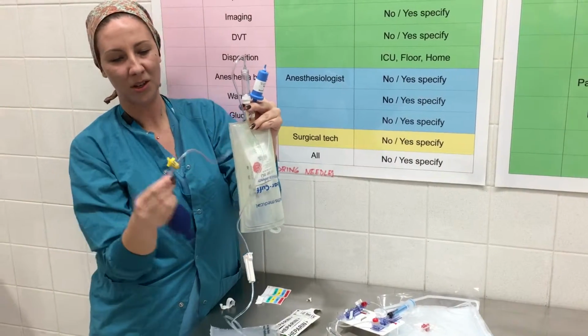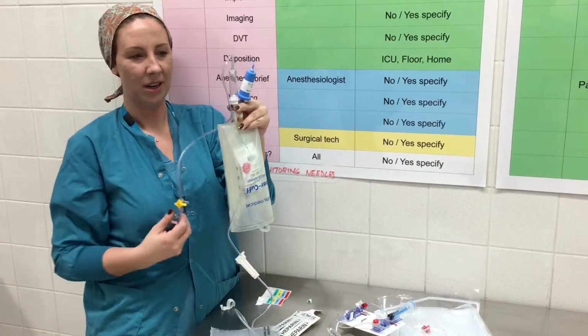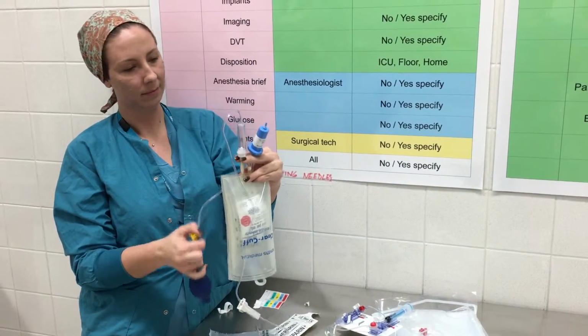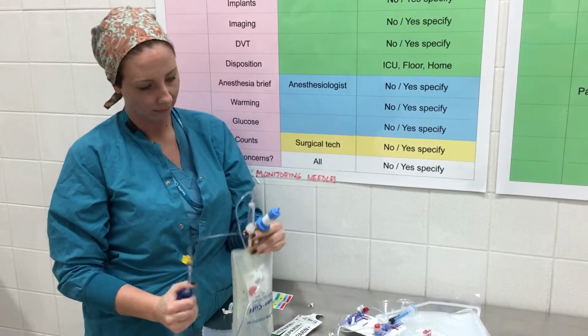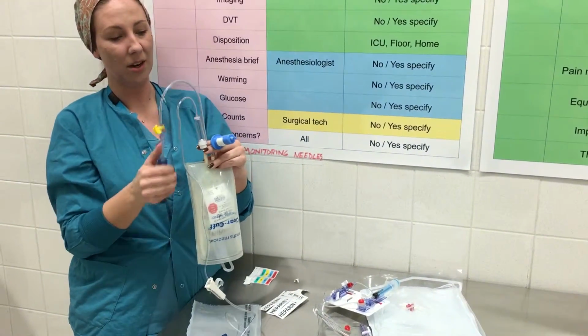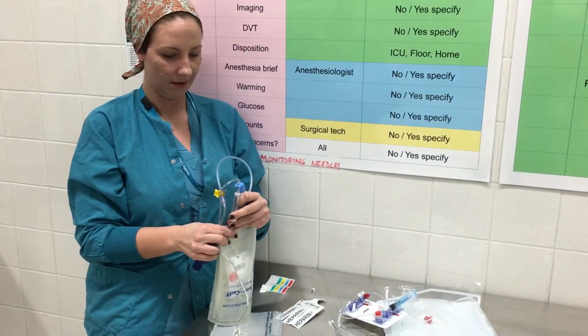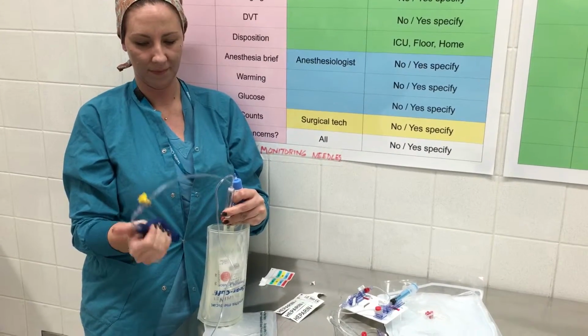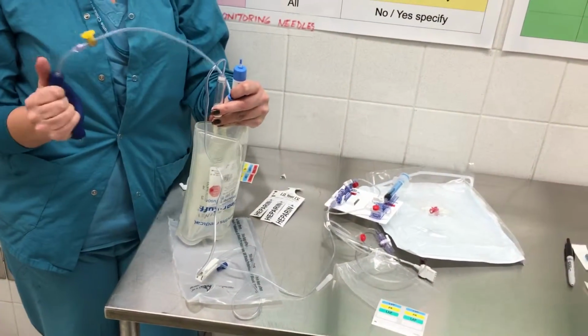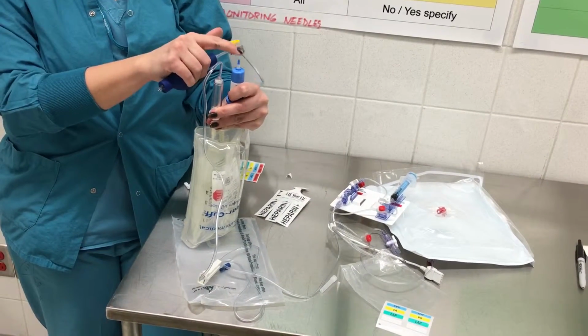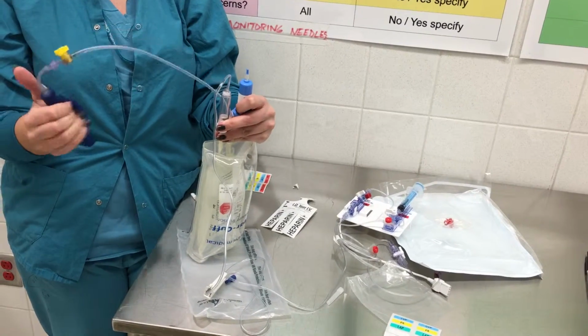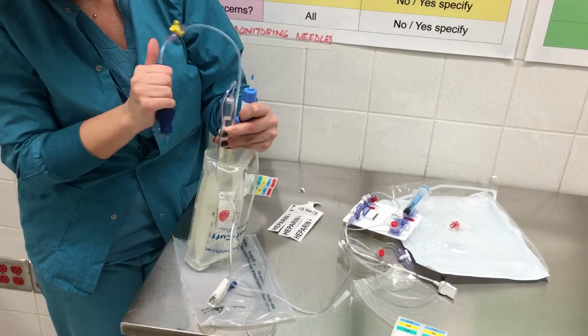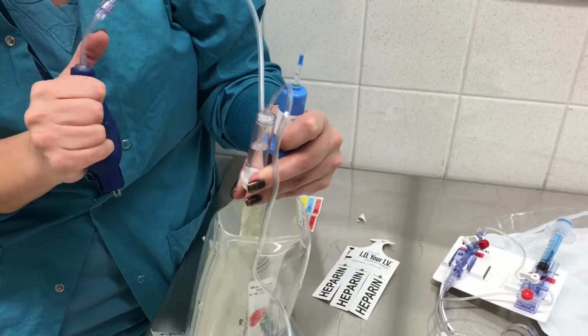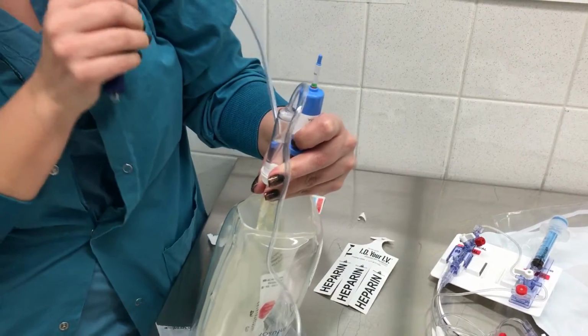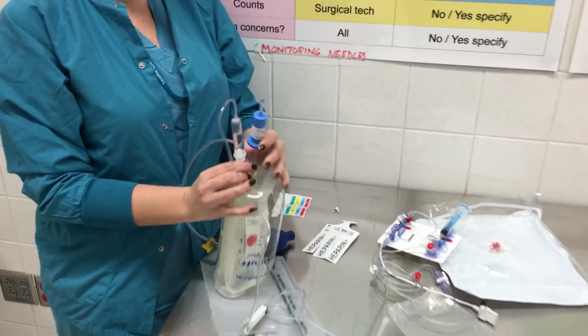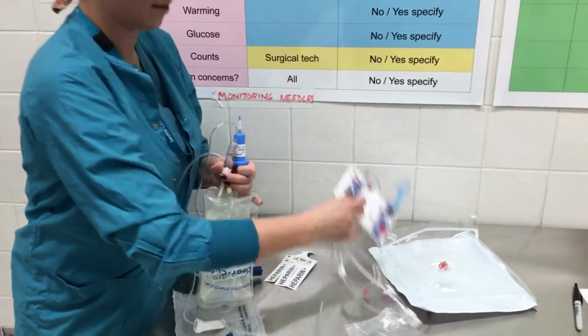So then you make sure that your stopcock is on the lock, the releasing valve, and you can start pressurizing. My thing was kinked, so I couldn't do it. As you're pressurizing your bag, you're going to watch this tip here, and it'll go from white to green to red, and there's units of pressure on there. You want to bring it right to where you see the red. And then this is where we want to start when we start priming.